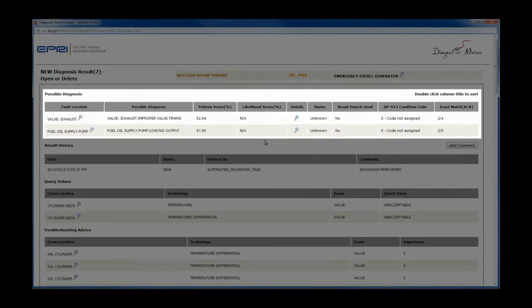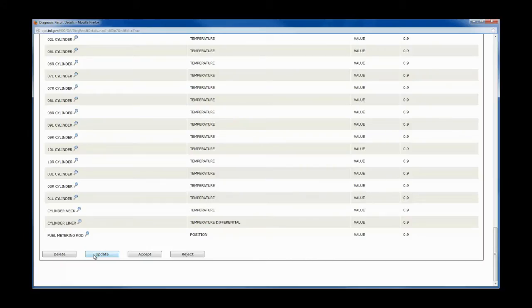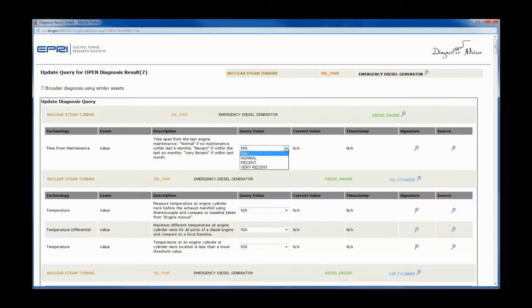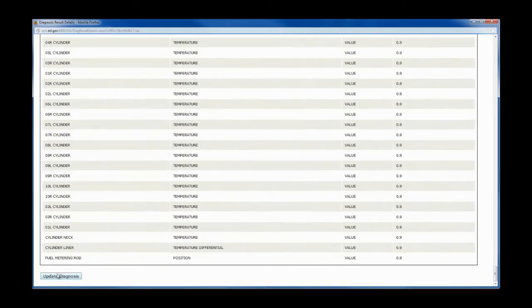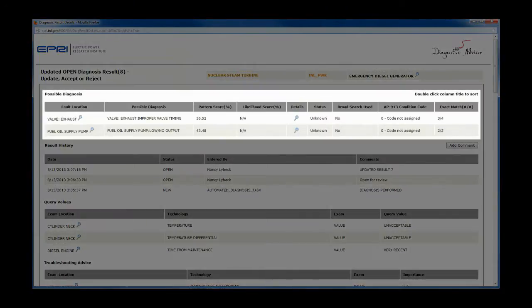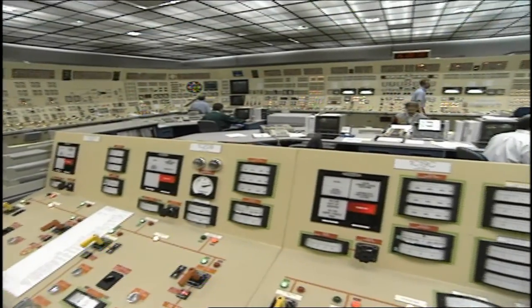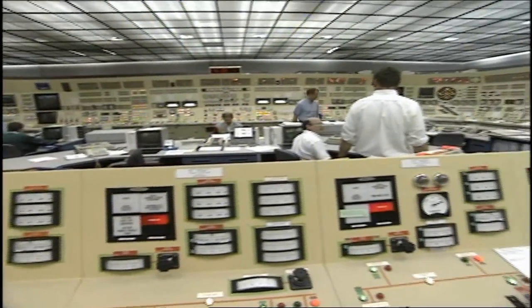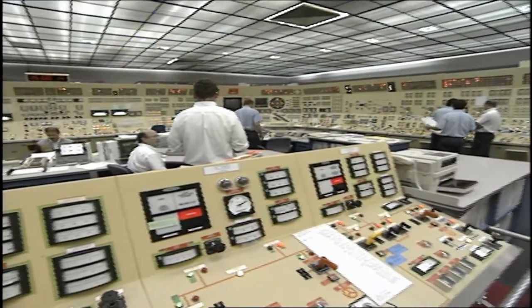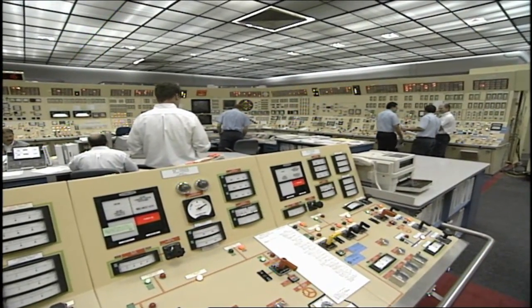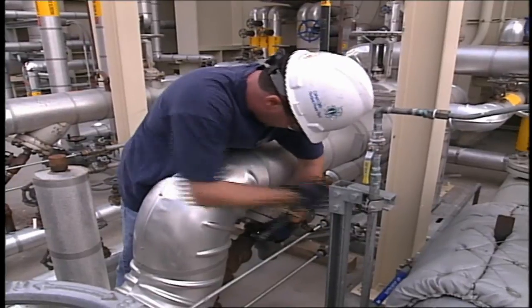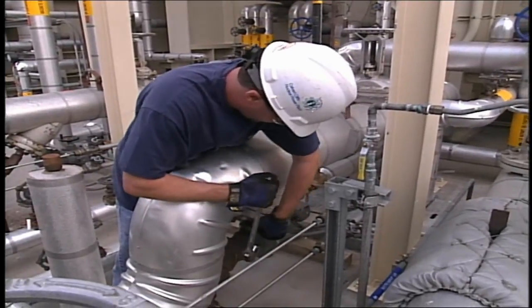The diagnostic result can be opened for review. The engineer in charge can input additional information by updating the open diagnosis. Entering the information that a maintenance action was performed very recently modifies the diagnosis to more strongly support the improper valve timing fault. This demonstration highlighted the ability of the Diagnostic Advisor to take advantage of all information that might influence a diagnosis, including information from periodic inspections and maintenance actions.